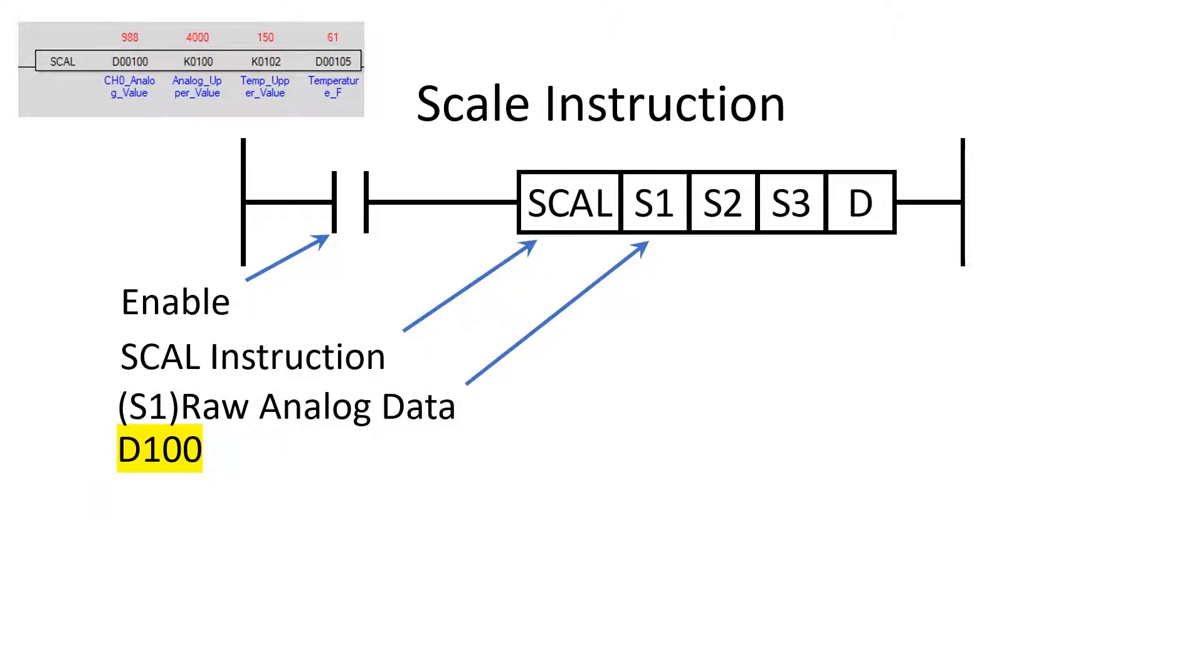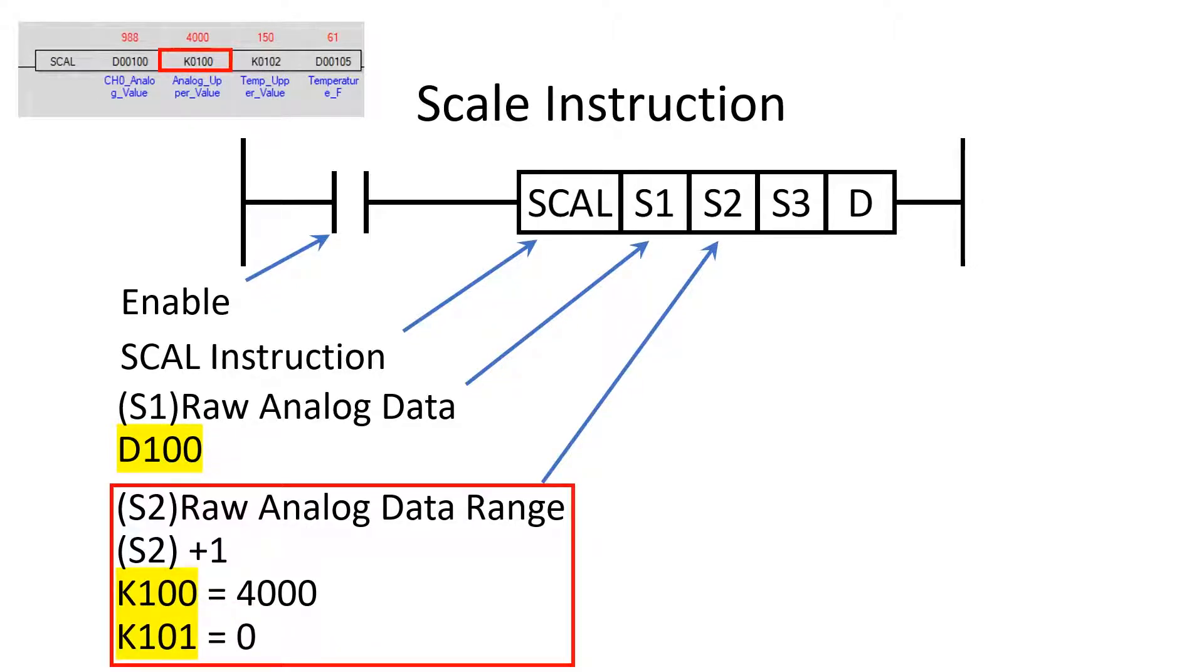Operands S2 and S3 are stored in K memory as this is retentive memory. The S2 operand is the memory location of the upper value of the raw analog range. This analog channel is set up with a max count value of 4000.